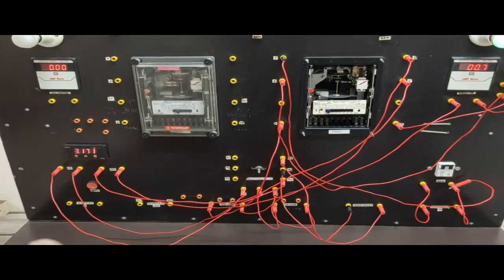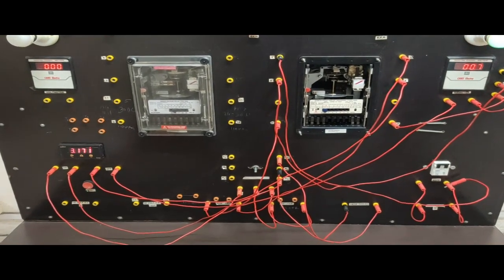So in this way all the relays are operated. One single electromechanical relay is not fixed for a particular current or time. According to the requirement of the user, and according to the apparatus which needs to be protected, the time of operation as well as the current through the relay can be controlled using these two settings.